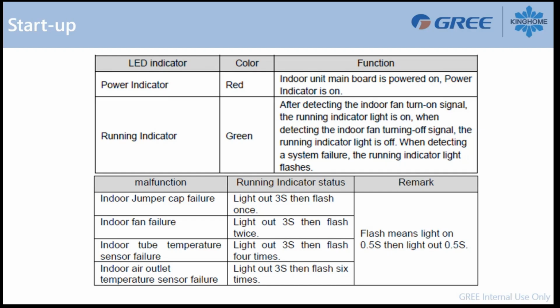You also have a green LED. This one tells you the system is turned on, so now the system is running. If you don't have any call on the system, this light will turn off. You also have a malfunction chart regarding this green LED. For example, if you see this green LED flashing, you will have to count the number of flashes and then take a look inside the user manual, and maybe you will find your error codes regarding this green LED.